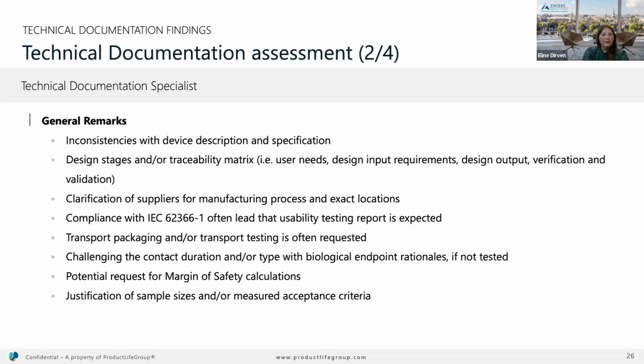Sometimes we see a request for a margin of safety calculation. And I think Emmerich already addressed it: justification for sample sizes, and also to have the measured acceptance criteria already mentioned in the protocols. That's essential. And that's also what we see coming back a lot.